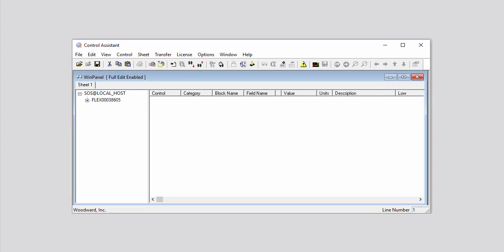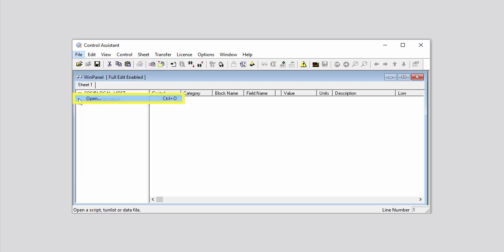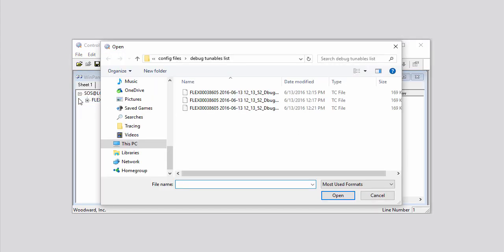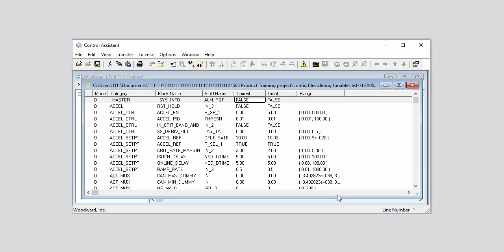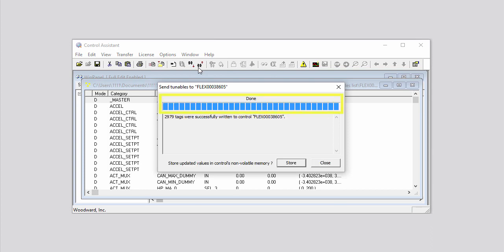You can also use Control Assistant to open an existing TC file from your computer and then send it to the controller. To do so, click File on the menu bar, then click Open on the drop-down menu. In the Open dialog box that opens, navigate to the location of the existing tunable file, select it, and then click Open. Click the Send Tunable List icon on the toolbar. In the Send Tunables pop-up window that opens, wait for the word Done to display at the top, then click Store.